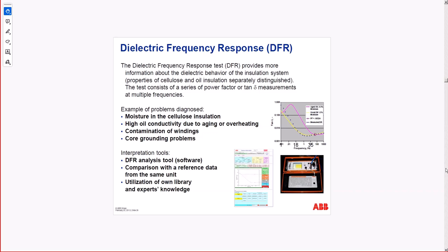Dielectric frequency response. Here is the curve. You can see it's from 0.001 to 1000 hertz. Each point is actually a power factor of the insulation. You see power factor there 0.0324 and so on. So dielectric frequency response provides information about the dielectric behavior of the insulation system, with the properties of the cellulose and oil insulation separately distinguished.